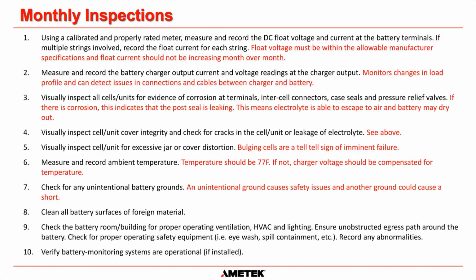Also, during a monthly inspection, you should check for any unintentional battery grounds. An unintentional ground causes safety issues. Basically, your battery is in most cases supposed to be floating. In other words, it has no reference to ground.